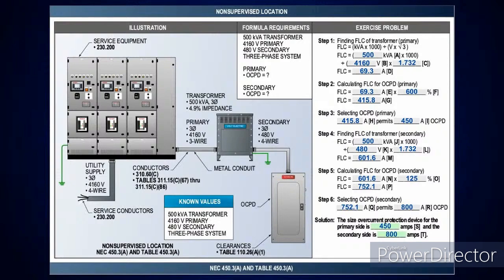Now the primary is 4160. It's three-phase, of course, and the secondary is 480 volt, three-phase. So I'm going to do the same calculation, just like we discussed when we first started all this. I've got my kVA there, times 1,000. So I got a 500 kVA transformer, times 1,000, 500,000. So I'm going to divide the voltage into that. It's going to give me 69.3 amps. Now, as I look at any location and I come across, and I'm doing the primary protection here, and I'm doing circuit breaker here, you're going to see it's at 600%. Okay? So I'll take 69.3 times 600%. It's going to give me 415.8 amps. I have a superscript 1 there, so I'm going to go up to the next standard size per table 240.6(A), which is a 450 amp overcurrent device.